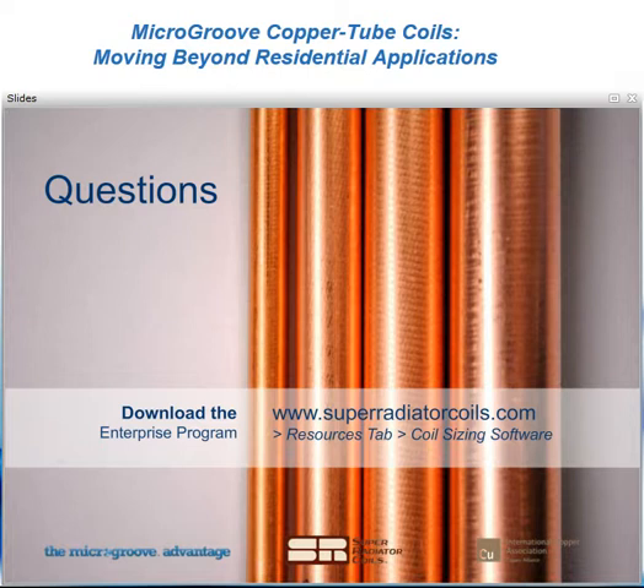When you're looking at other technologies, say microchannel, where sometimes depth has become a problem, there is no depth of rows limitation in manufacturing these coils. So we have confidence we can build them larger than 100 inches. What we found, though, is that manufacturing capabilities are not proving to be the limitation. Really, the pressure drop and the circuiting management have proven to be the limitation. If I were to answer in terms of capacity, certainly we've designed and built units with, I think, a 45 or 50 ton rating, and we see no reason why we can't go beyond that.